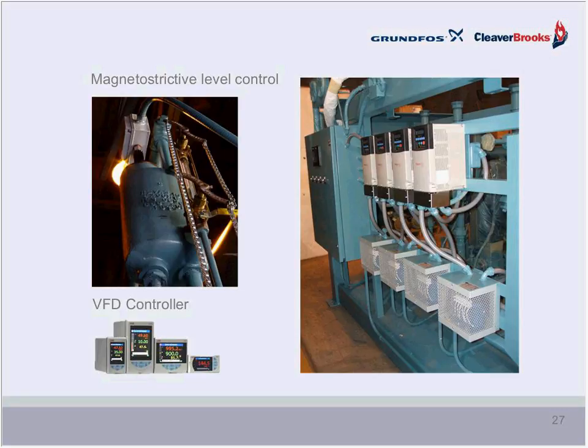Or there is another option that Jim will be discussing shortly, and that is eliminating the feed valve altogether and just using the 4 to 20 milliamp signal from the level control and sending it directly to the VFD drive.